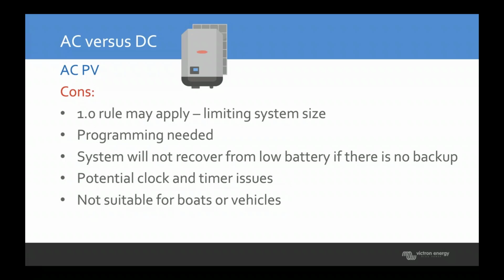The system will not recover from low battery if there's no backup. You have potential clock and timer issues. The situation with how the systems communicate is through this frequency shift power control. Normally when the system's happy in Australia, it's running at 50 Hertz, and at 50 Hertz, the Fronius will give full throttle to the Multiplus in the system.